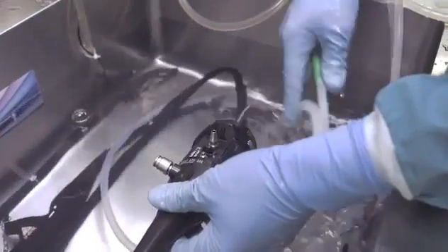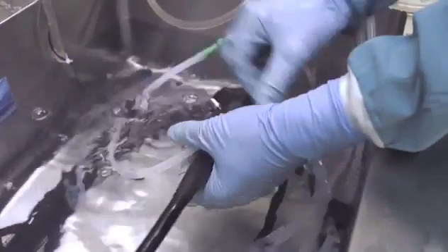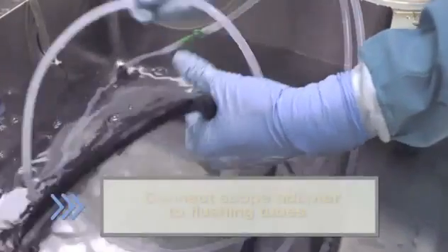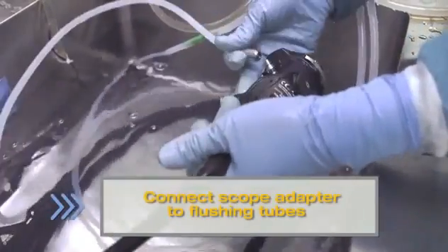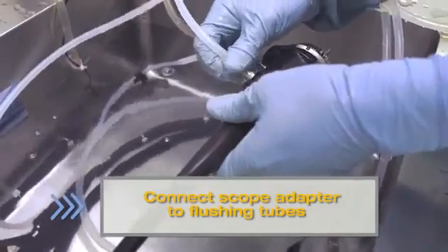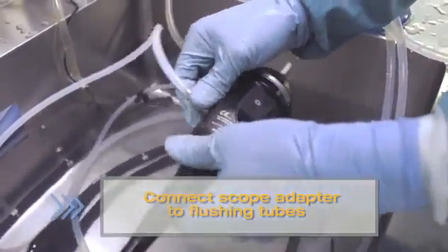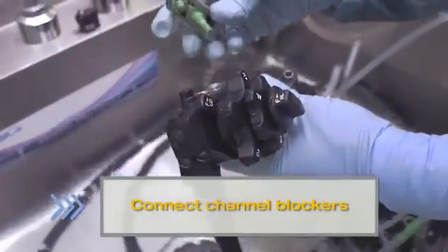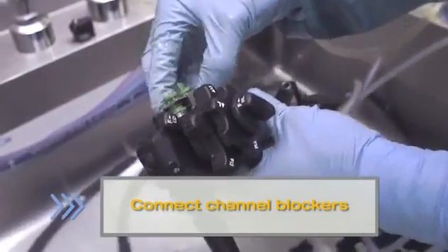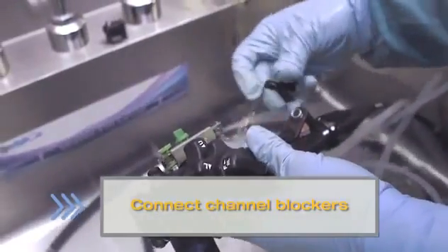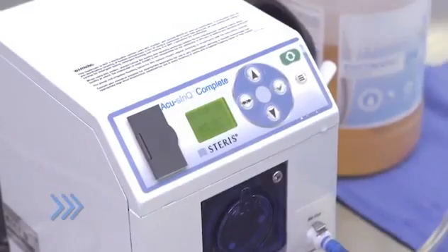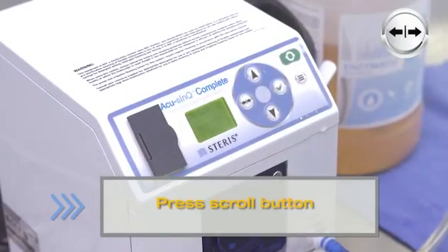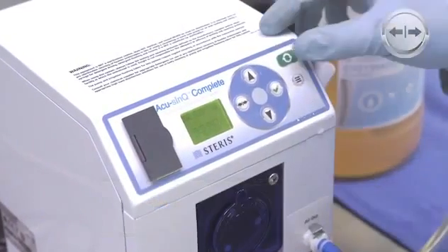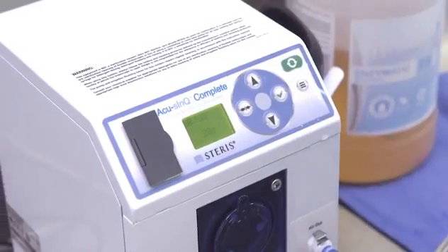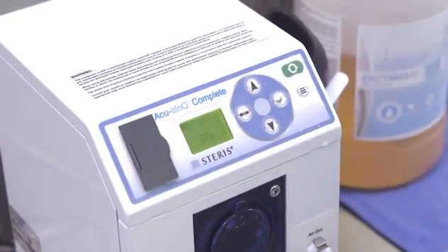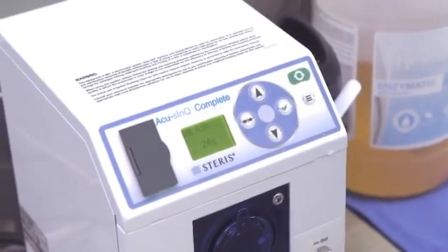Next, you will perform a scope flush. First, gather flushing tube with the appropriate port adapters attached and connect to the endoscope. Then, connect channel blockers. Now press the scroll button to choose a single or dual flush. Then press Start to begin flushing. Allow the timer to count down to 0.